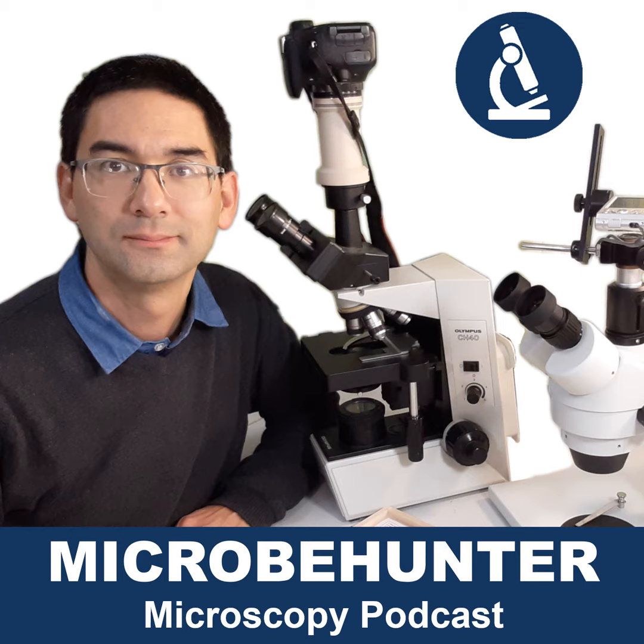Okay, that's a big one. In many cases, the microscopes have already, let's say, the 10 times or the 40 times objective rotated in place, and sometimes beginners simply continue to use the objectives that are currently rotated into position. Sometimes these are high power objectives, but that's not the objective that you're supposed to start with.